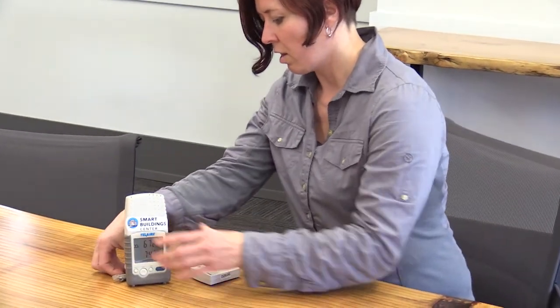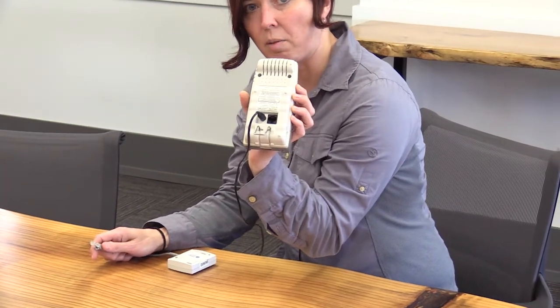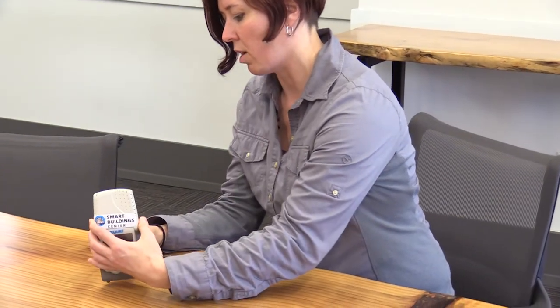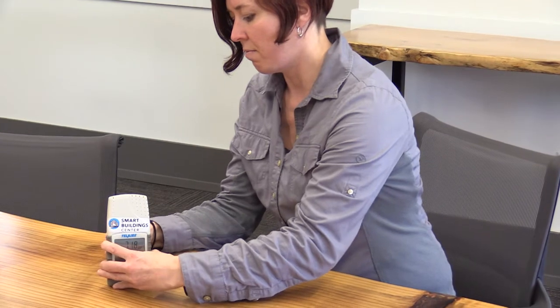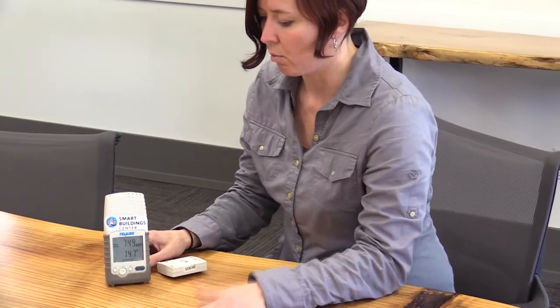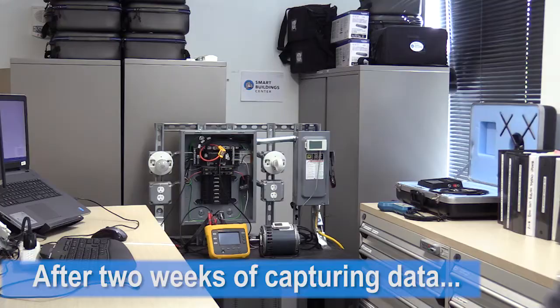Then I've got a Cat5 style connector on the back of this Telaire, so I'm just going to go ahead and plug that in. And voila, we're ready to go. So I'm going to leave these sitting here for at least 2 weeks so that we can get a sense of what's happening with the CO2 levels over occupied periods, unoccupied periods, weekdays, and weekends.